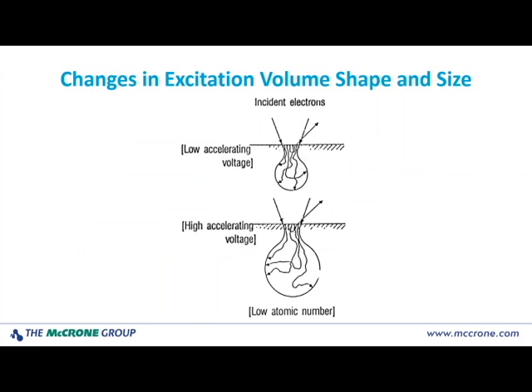The typical shape if we're looking at a piece of carbon is what's called a teardrop or pear-shaped excitation volume. We're rastering the area at the surface, but then it impinges into it, goes down a little ways, and starts interacting with the electrons and protons in the atoms of the specimen, and it swells. If we go from a low accelerating voltage to a higher accelerating voltage — maybe 5 kV to 30 kV — the excitation volume merely gets bigger: it swells, gets deeper and wider. So always keep that in mind.